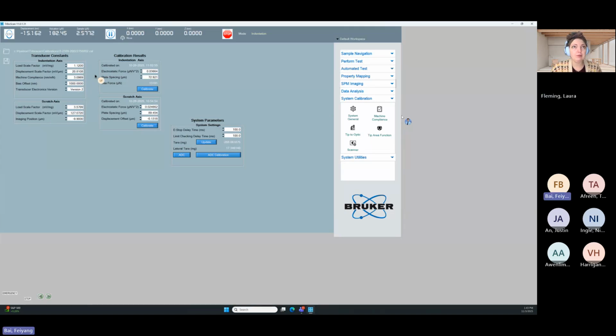Is that an inspection report? No, it's usually in the transducer box itself. Oh, the transducer box. Mm-hmm. Yes. Good. I have the indentation axis and the lateral axis. Yes, I have this document. 1.12, 20.8108, and the machine compliance, and then the bias offset is not on this paper. The paper has the electrostatic force constant, then the plate spacing, and then the maximum force.